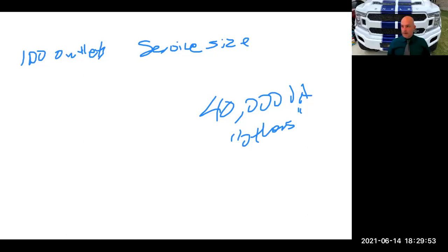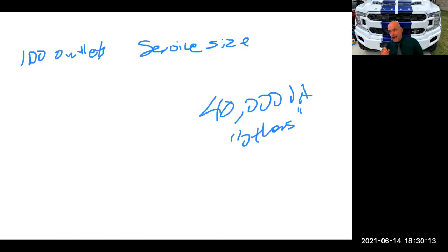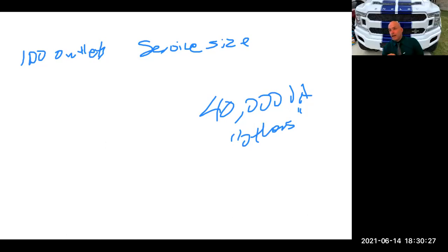But we're talking about a service calculation, so we're looking for some sort of allowance to use 220.44, which is on the next page over. If it's an office or a bank, that's where it gets tricky. 220.14(K) is the controlling article in this question, because this office or bank would be treated a little differently than a restaurant or some other commercial building. K1 says, do it just like you would under (I), and I would allow you to take the derating if you were allowed to. So you would derate section (I).